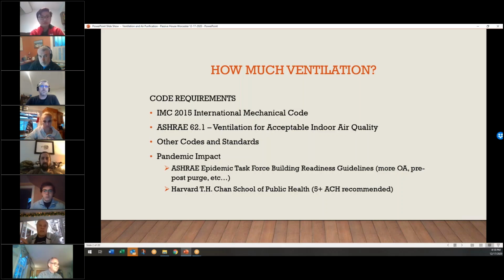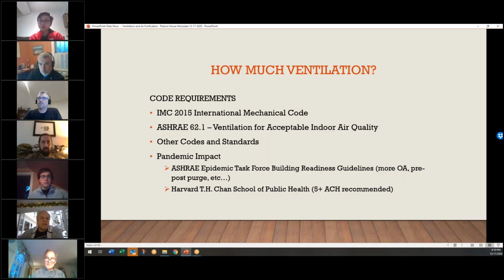It provides a lot of insight on a lot of different measures, but as HVAC goes, the main crux of it is providing more outside air within the limits of your mechanical systems, right? Because some systems, you can't just provide 100% outside air. It was never designed for that. You may be able to do it in the spring and fall, but you can't do it in the dead of winter.